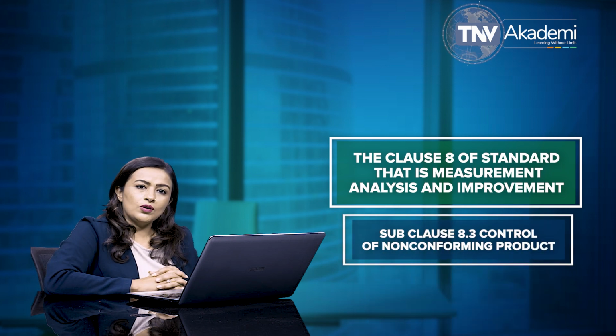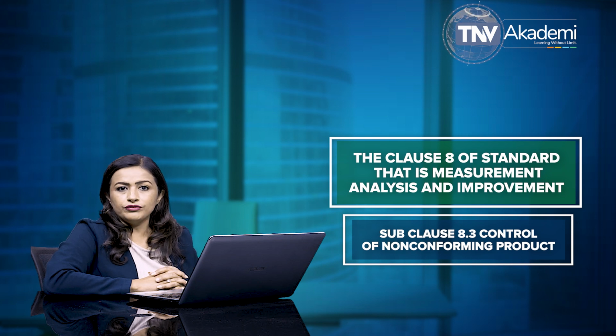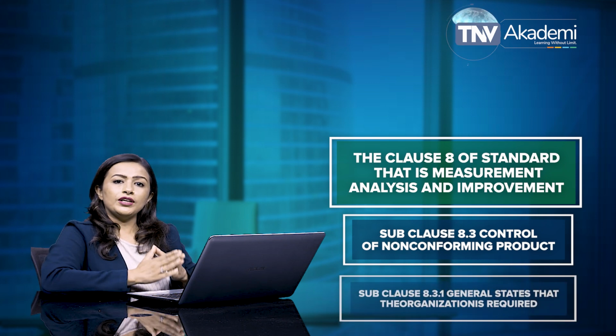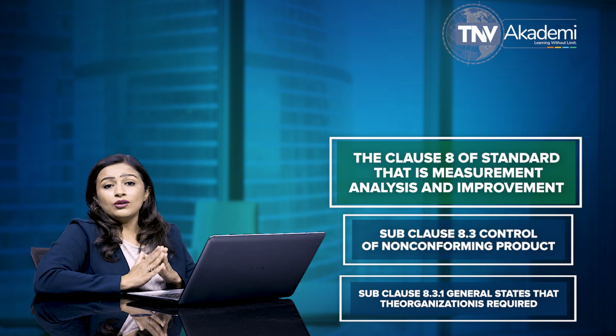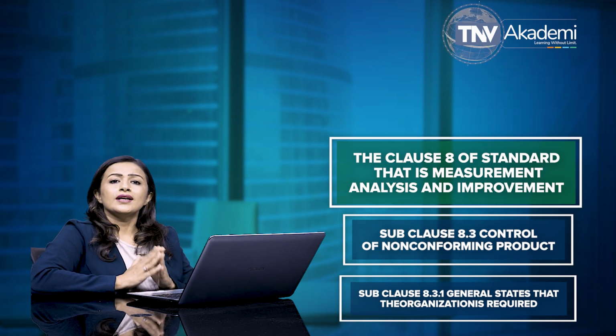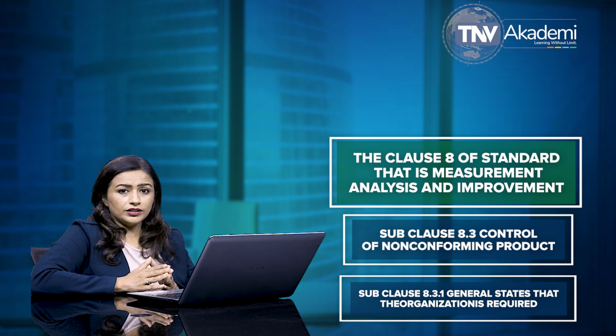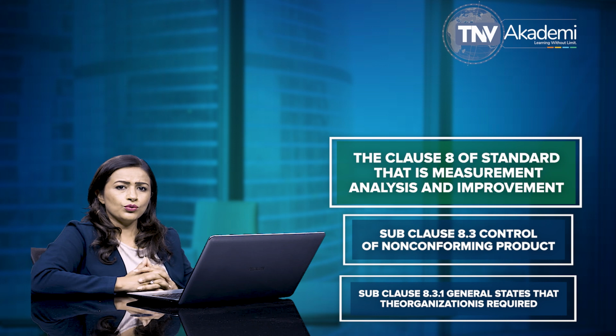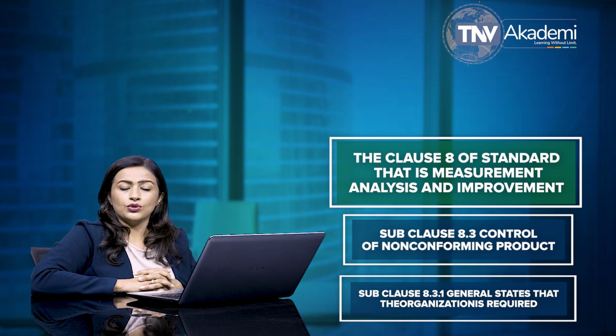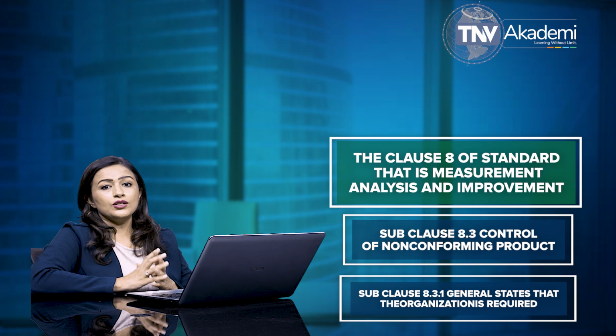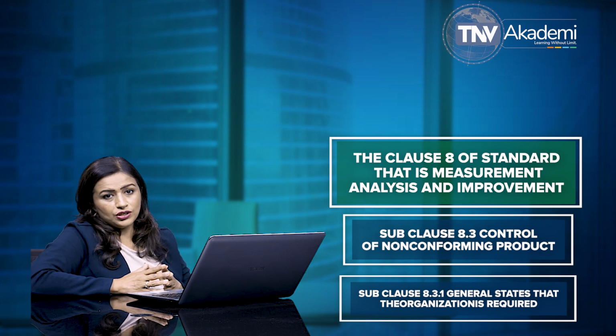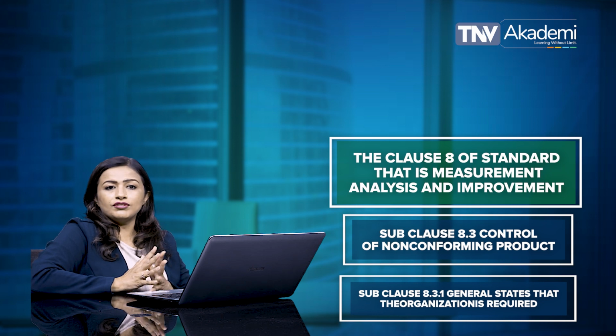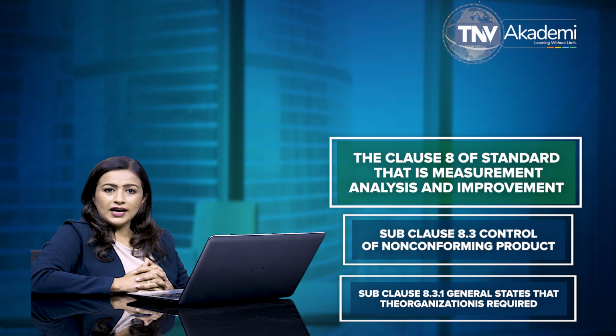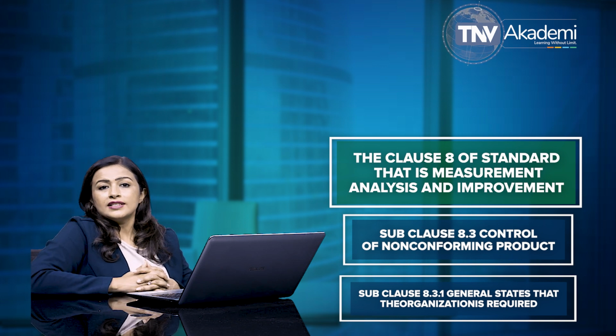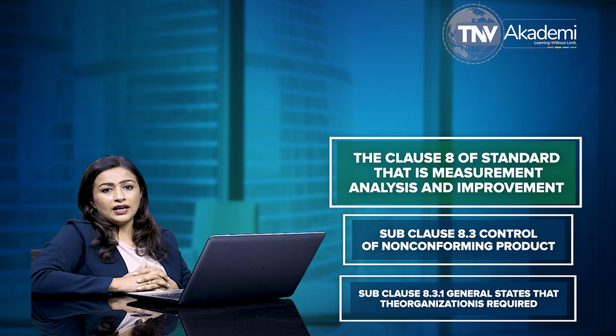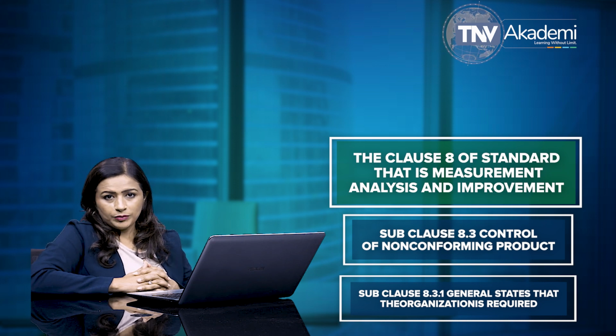Let us talk about subclause 8.3, control of non-conforming product. Subclause 8.3.1 general states that the organization is required to ensure that product which does not conform to product requirements is identified and controlled to prevent its unintended use or delivery. This clause says that the organization must document a procedure to define the controls and related responsibilities and authorities for the identification, documentation, segregation, evaluation, and disposition of non-conforming product.